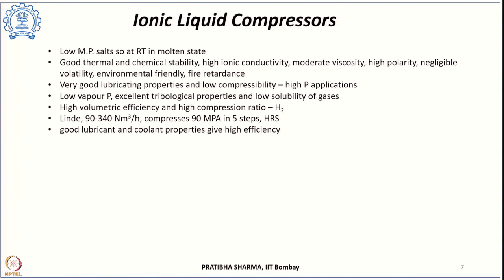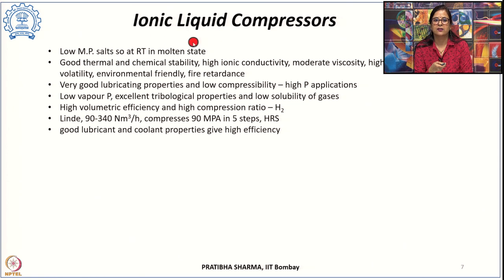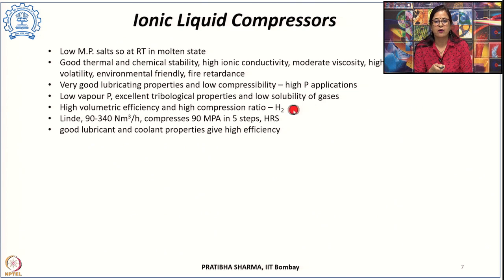Ionic liquids have very low compressibility, making them ideal for hydrogen compression, and using these ionic liquid compressors we can achieve high pressures. The working principle is the same as other liquid compressors; the only difference is the liquid used is an ionic liquid. This ionic liquid has a low vapor pressure, very good tribological properties, and low solubility of hydrogen, ensuring very low loss of hydrogen. These compressors are highly volumetrically efficient and can provide high compression ratios. The well-known Linde company produces ionic liquid compressors.